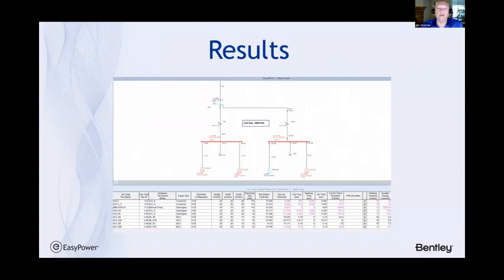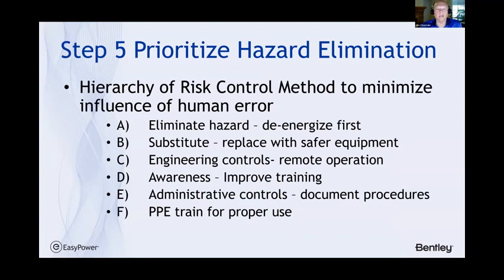So the results end up being you have a well-documented one-line diagram. You have the ability to calculate incident energy, both for normal events and for the need to do mitigation. And at that point, you want to prioritize hazard elimination. Justin referred to this as well. It's called the hierarchy of risk control methodology to minimize the influence of human error. In the early days of NFPA 70E, including arc flash, the whole focus was putting on more PPE to keep people from getting hurt while they're working on the equipment.